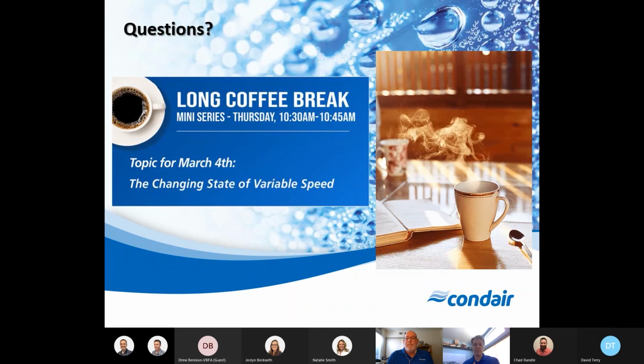Very good. And I often remind a lot of people, especially with the electric type of humidifiers that we have, to think of it not just as your humidifier, but think of it as your water quality filter. If you can combine both of those in a humidifier, they say, oh, they have too much maintenance. Well, you could filter that with an RO skid, which again, RODI skids we offer through Condair. You could use that up front of a unit and have no maintenance on the humidifier, but now you've moved that maintenance. So a lot of the electrode steam that we see, it's kind of the nature of the beast. You have to have that maintenance somewhere. And looking at your humidifier and the electrode steam as a filtration and a humidification device, I think helps the owners understand some of those differences and the maintenance required.